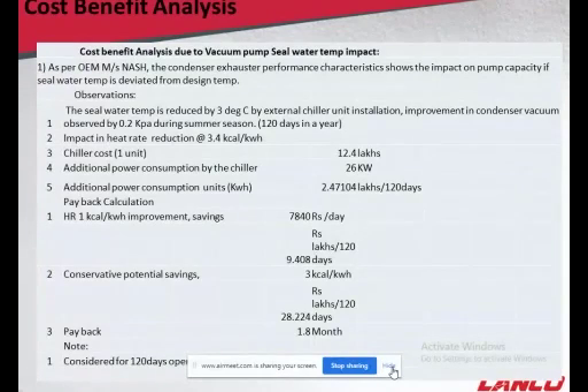So the overall cost is about 12.4 lakhs. There was an excess power consumption of 26 kilowatts, but with the overall improvement in the vacuum, for 100 days of running, the payback period was less than 2 months. So this was one of the great achievements in the vacuum system for improving heat rate that we have.